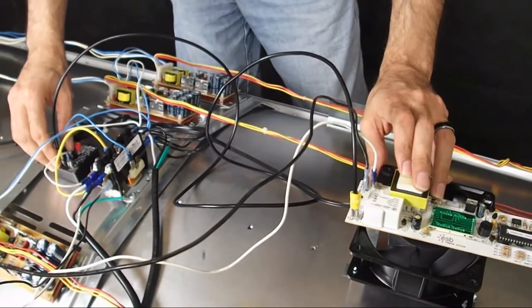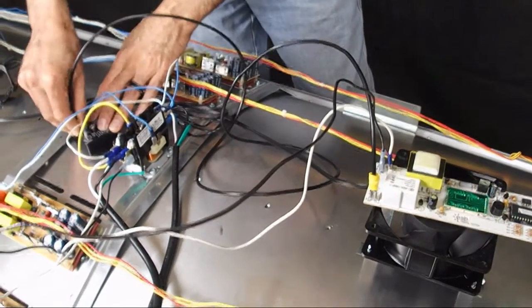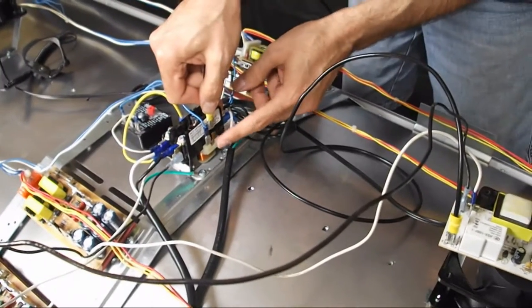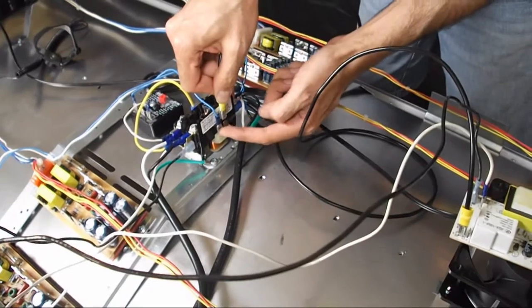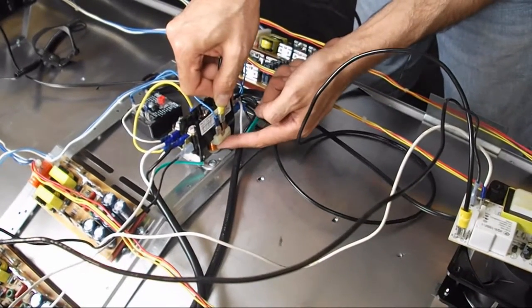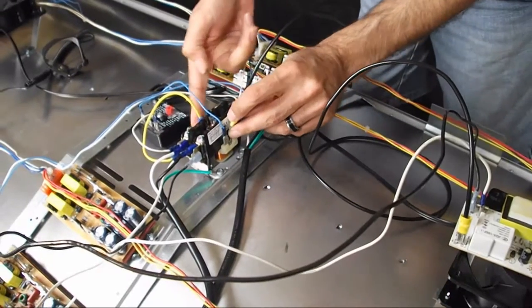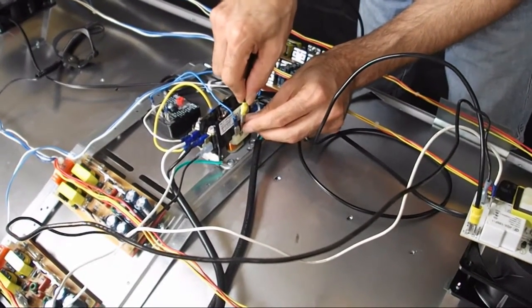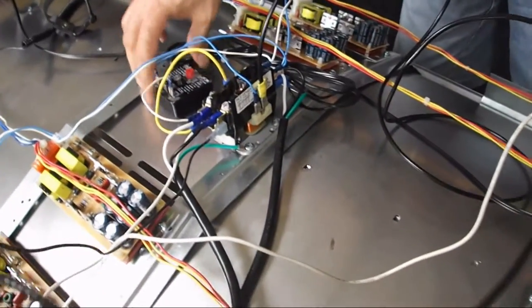So, like I said, the models that do not have a backup timer over here, instead of connecting it to the backup timer, what you would do is you would take this wire and connect it onto the very side terminal here of your contactor. There's only two terminals here, and these go down to your coil here. And it's on the hot side, opposing here on the neutral side. So, either of the two terminals will be fine. And then, that's how you would connect it if you do not have a backup timer.